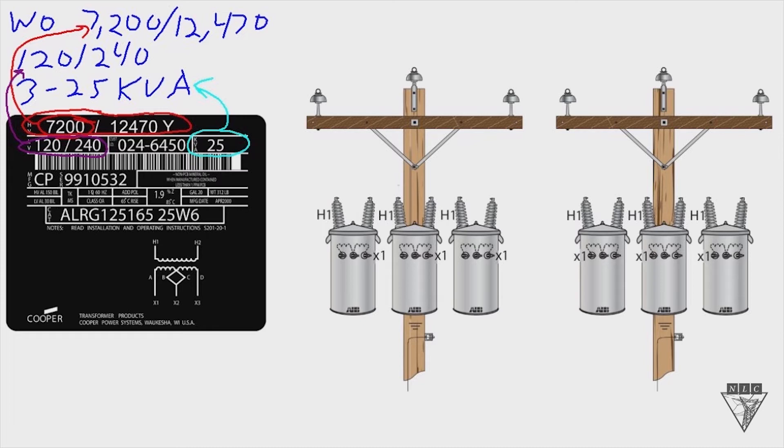So there's the first three things we need: the circuit voltage matches on the transformer voltage rating, then the service voltage is a match and the size of the transformers is a match.